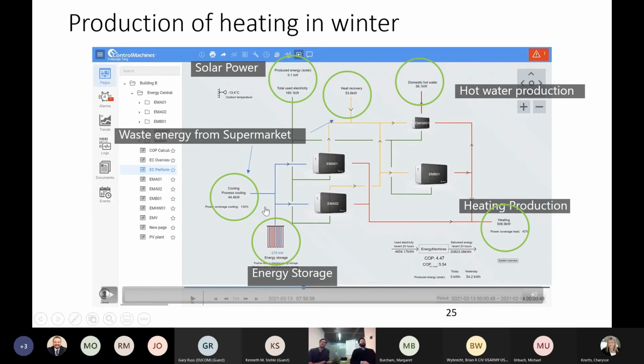On the left side here we have the cooling coming in - both comfort cooling and process cooling, from the air conditioning of the building. So it's not using rooftop units that blow away heat from the condensers on the roof into the air. The reject heat there is routed into pipes along with the waste heat from the supermarket coolers as well.